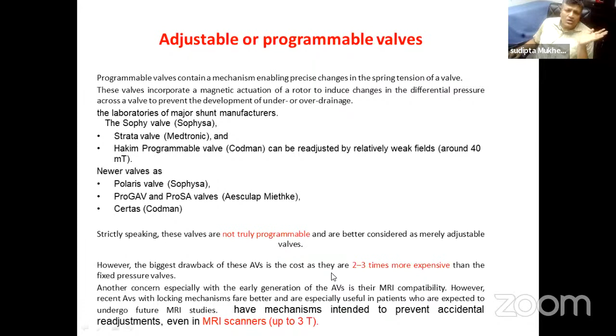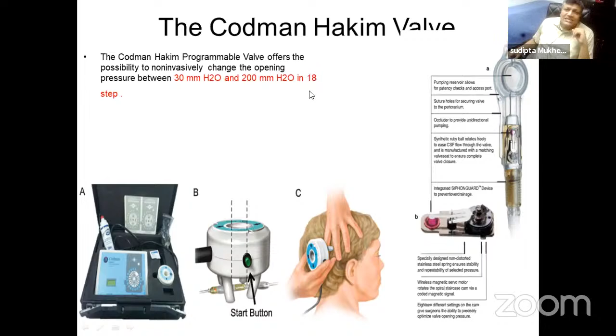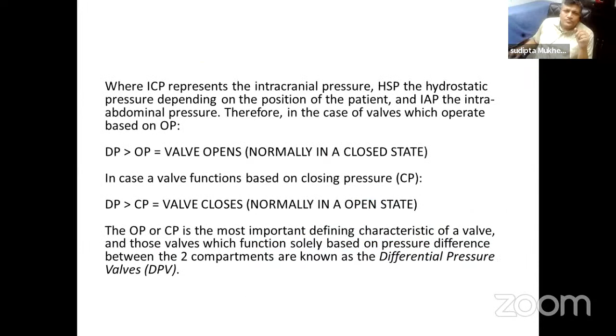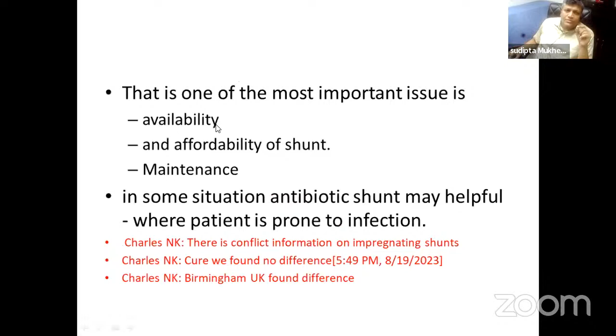So there are some examples of flow control valves. This is a Codman valve. This is the programming device working from outside. It has a foot, so the foot should be placed over the valve. So this is controlled by a magnetic device from outside. And see, it can control the pressure from 30 millimeters to 200 millimeters of water pressure. So it has 18 steps. That is one of the best valves from Codman. Now, an important point: availability, affordability, and post-shunt maintenance are important for a flow control valve.